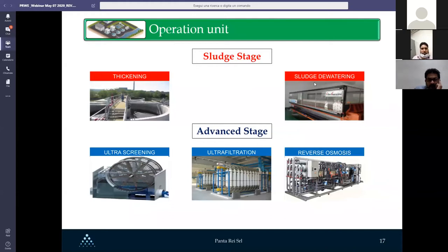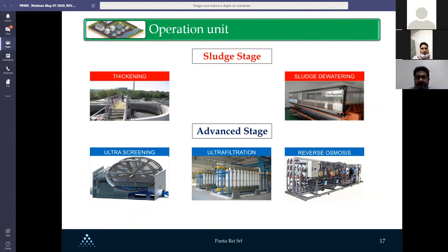The sludge stage consists of a thickener and then dewatering to get dry matter around 20–25% before disposal. If we take a step forward, we can also have an advanced stage for water recovery, which includes ultra screening with a 20-micron mesh, then ultrafiltration and reverse osmosis.